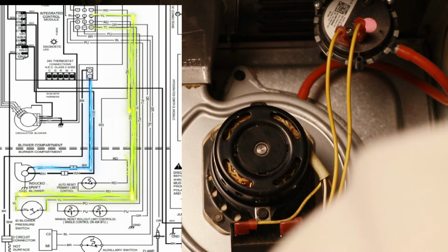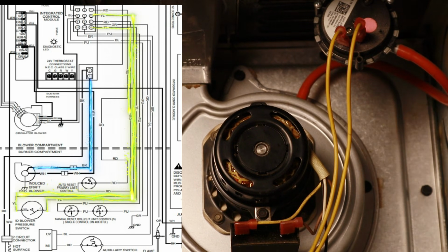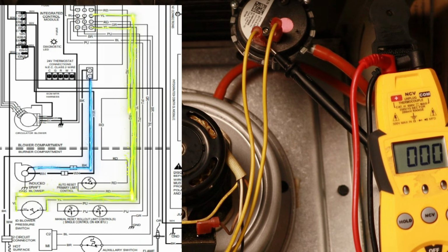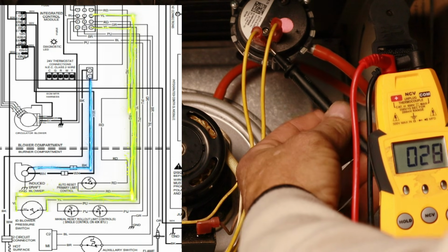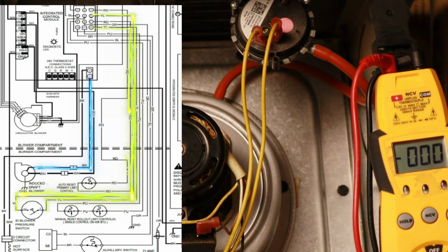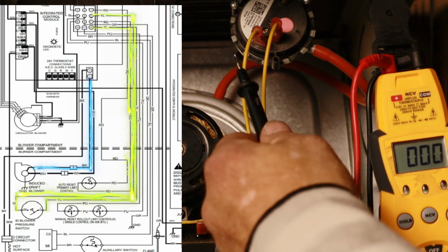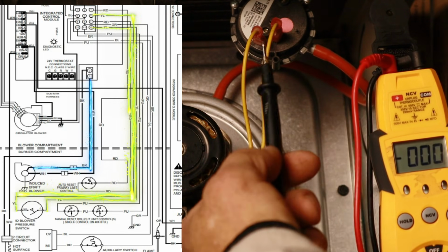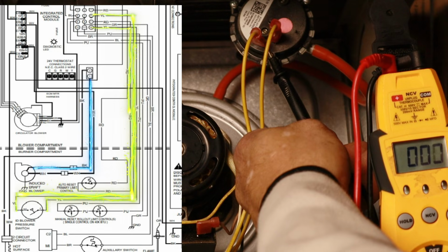So I'm going to go ahead and turn this furnace back on. I'm going to wait for the inducer motor to come on. All right, so my inducer motor came on. So what I'm going to do now is test for voltage going to this pressure switch to see if it's going in and coming out.